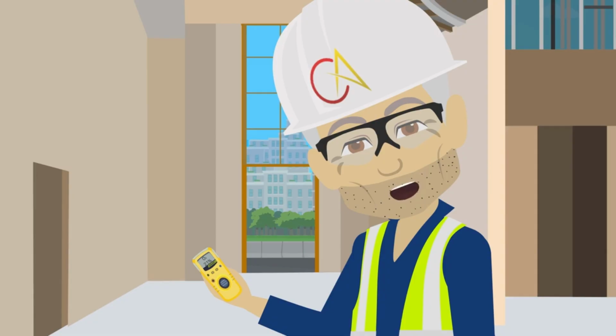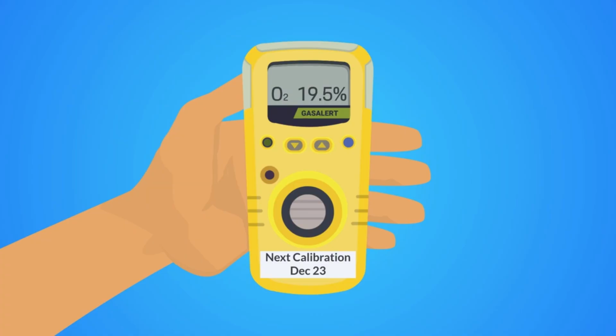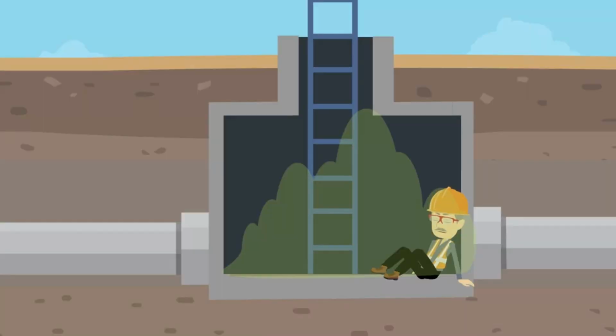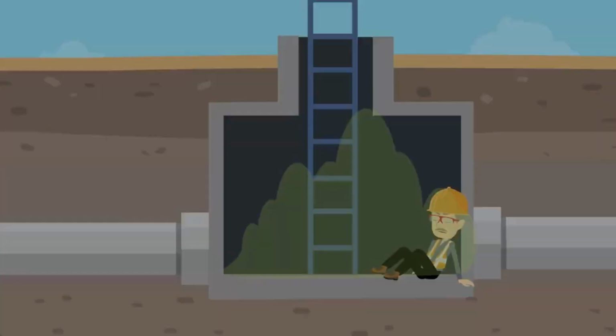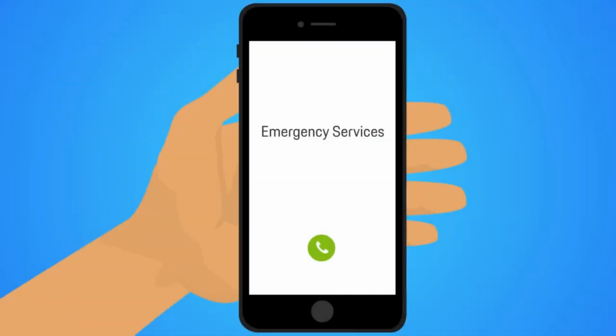The oxygen level of the air is 21%. Never enter a confined space if the oxygen level is below 19.5%, or due to the increased fire hazard when oxygen exceeds 23%. Never enter a confined space to rescue someone unconscious unless wearing a breathing apparatus. In such a situation, contact your local emergency services. They have the suitable equipment to attempt a rescue.